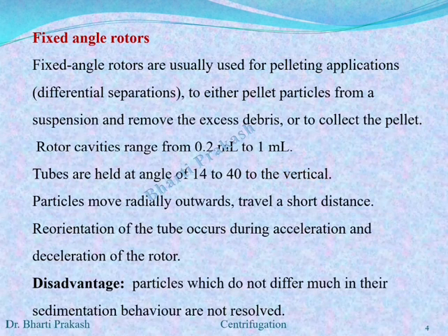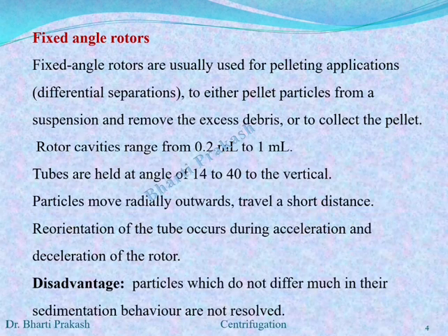Under the centrifugal field, the particles move radially outwards and travel a short distance before they strike the wall. The particles then slide down the wall and the pellet is formed at the outermost point of the tube. This sliding down makes the sedimentation quicker. This is known as the wall effect. What is a wall effect?